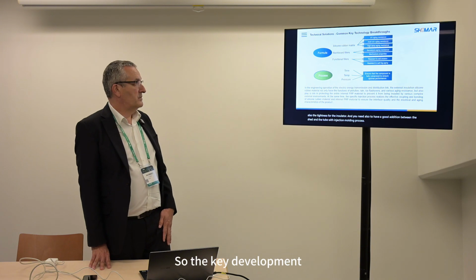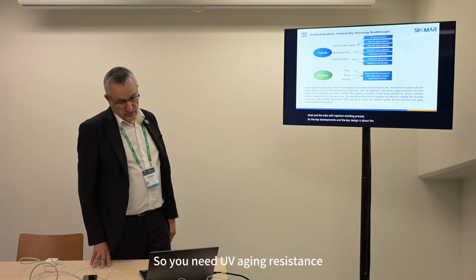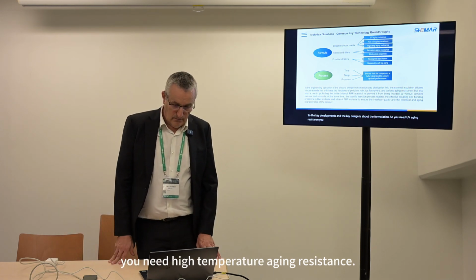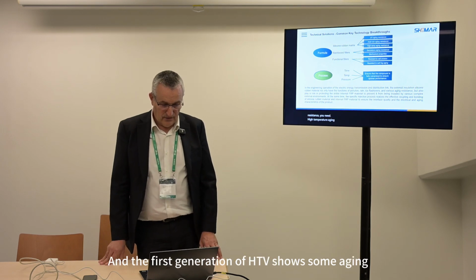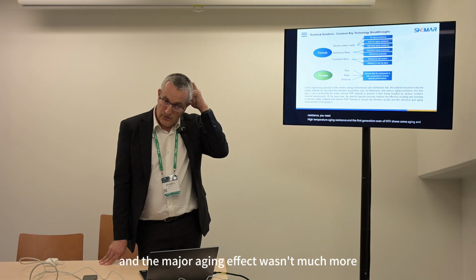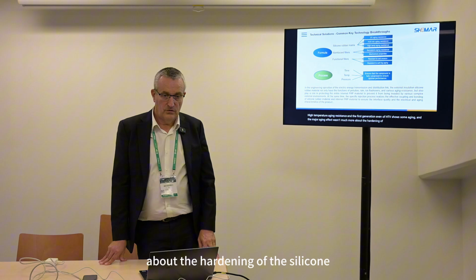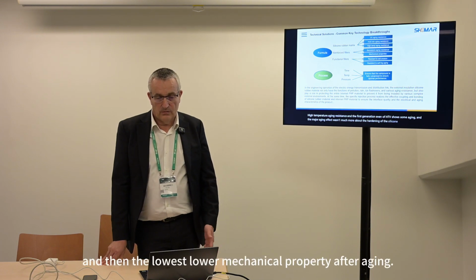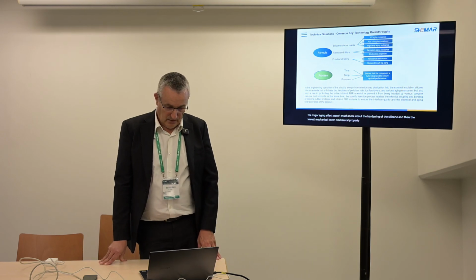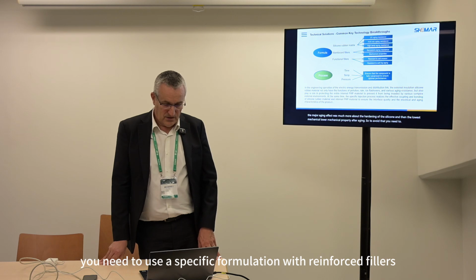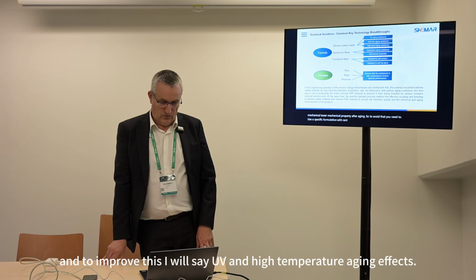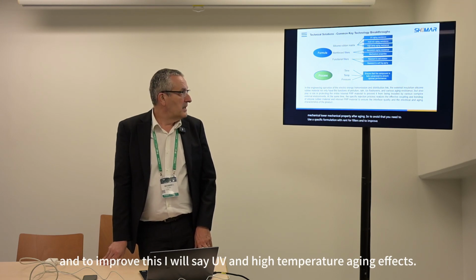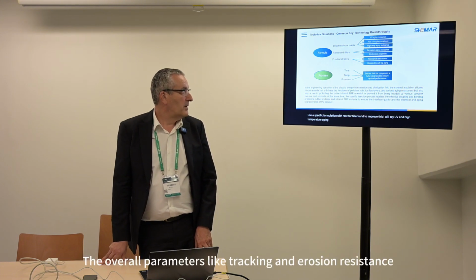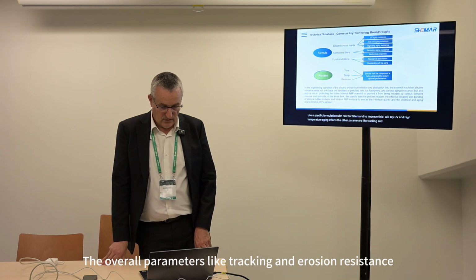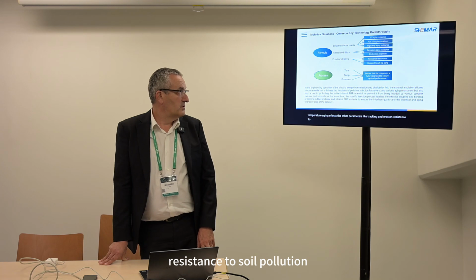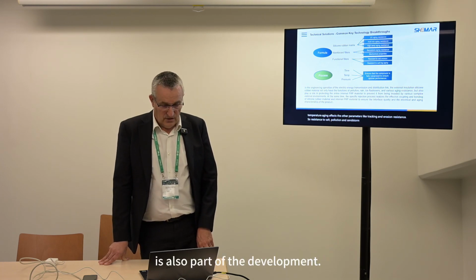So the key development and the key design is about the formulation. You need UV aging resistance, you need high temperature aging resistance, and even the first generation of HTV showed some aging. The major aging effect was the hardening of the silicone, so then lower mechanical properties after aging. To avoid that, you need to use a specific formulation with reinforced fillers to improve the UV and high temperature aging effects. The other parameters like tracking and erosion resistance, resistance to salt pollution, and sandstorm mechanical resistance are also part of the development.